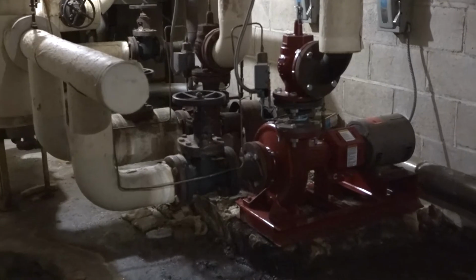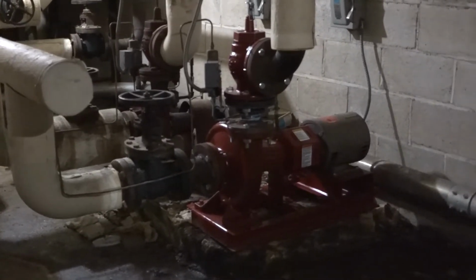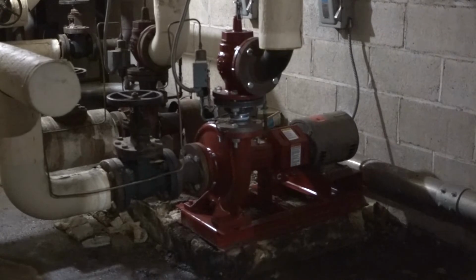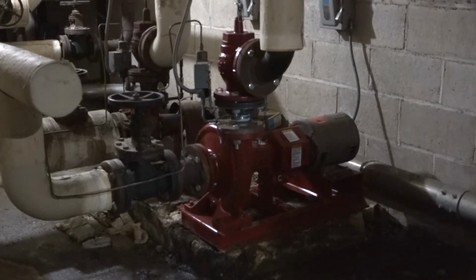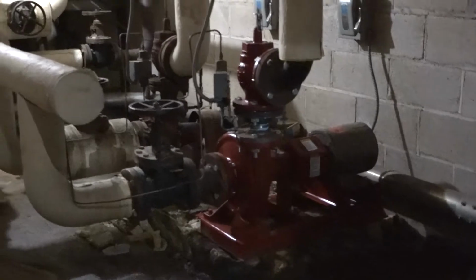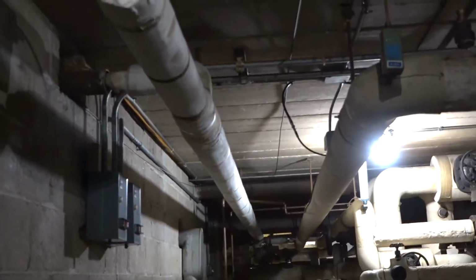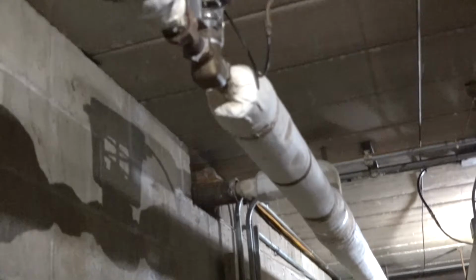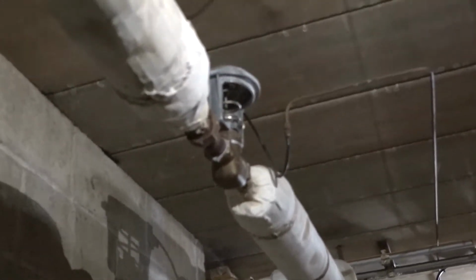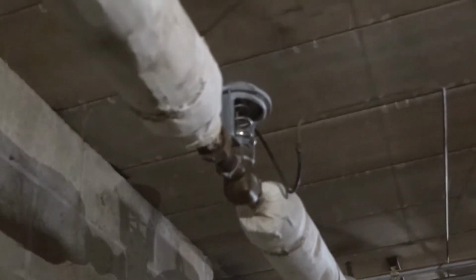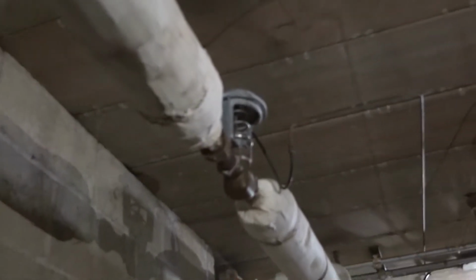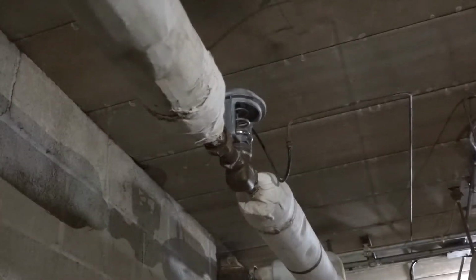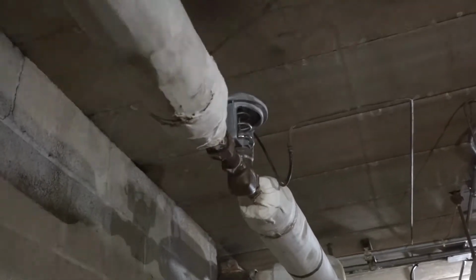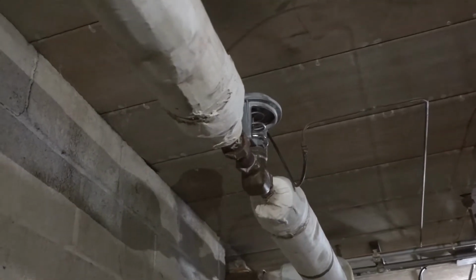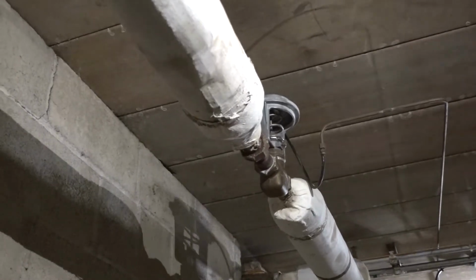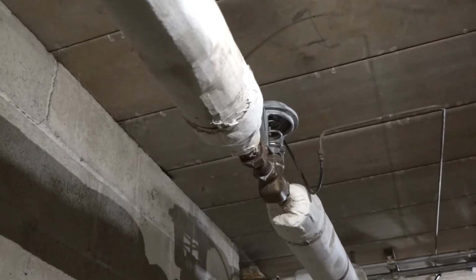So this is how the newer addition, the '57 addition, gets heated by hot water, as opposed to steam like the rest of the building. And as you can see right here, we still have pneumatic valves that operate the building off the thermostats. Those are throughout the building, in the tunnels, so not easy access to get to. So that's pretty much our heating system, from the boilers to the heat exchangers. And then through the rest of the building, it goes out pipes to heating valves like this one here.